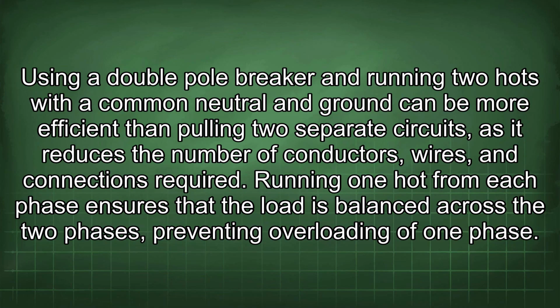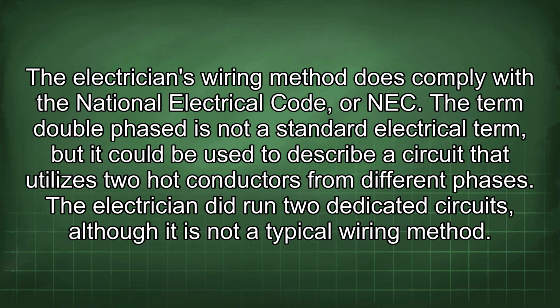Using a double pole breaker and running two hots with a common neutral and ground can be more efficient than pulling two separate circuits, as it reduces the number of conductors, wires, and connections required. Running one hot from each phase ensures that the load is balanced across the two phases, preventing overloading of one phase. The electrician's wiring method does comply with the National Electrical Code, or NEC.